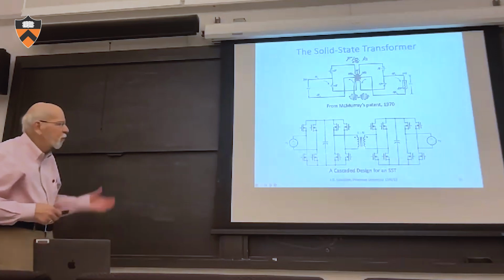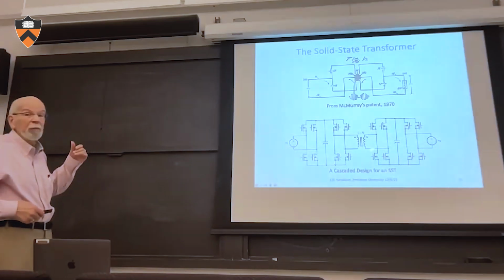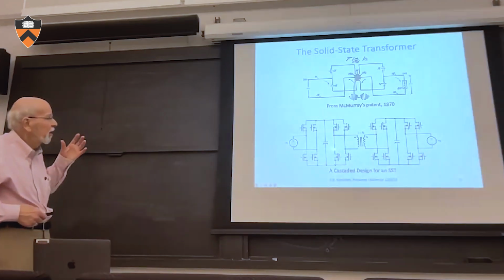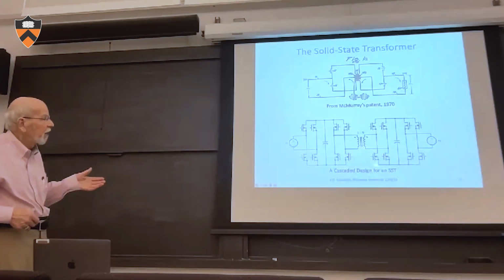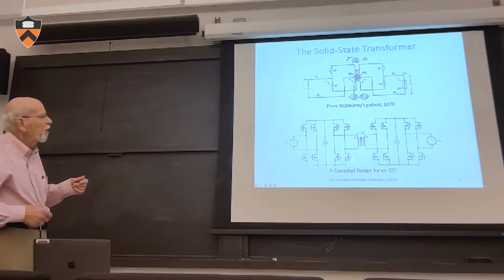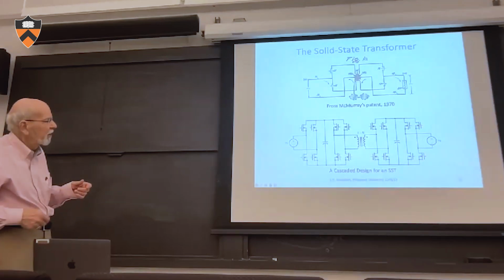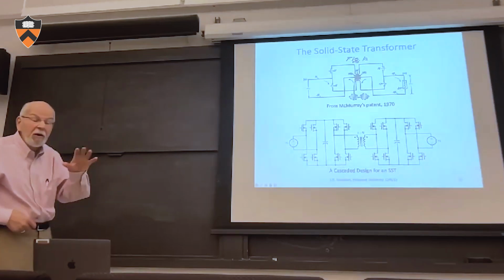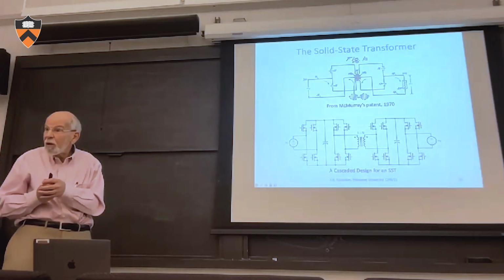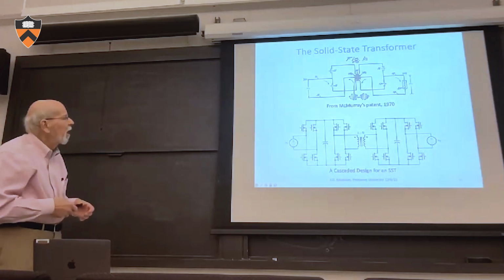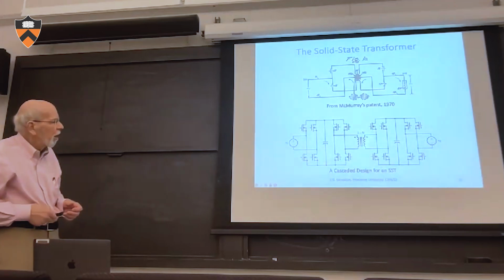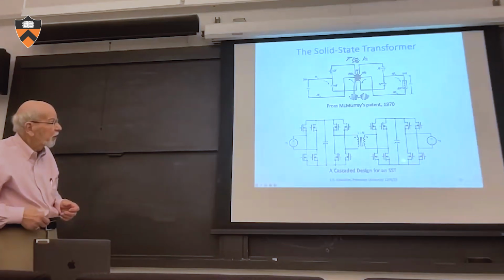Today, here's one design, not a very practical design because of so many switches, but it's a cascaded design for the solid state transformer. You've got AC coming in here, you convert it to DC. You've got a high frequency bridge that converts the DC to high frequency AC. You've got a transformer that, because it's high frequency, is small and relatively efficient. Then you convert that back to DC through this bridge, and then you convert it back to AC over here.